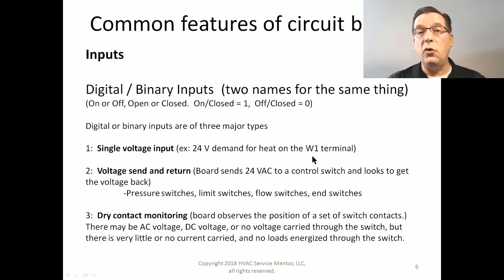Single voltage means there's one voltage it can be. It's either 24 volts or it's 0 volts. It's not in this kind of in-between varying type of throttling thing. No, it's either this or it's that. That's what we mean by binary. That's what we mean by digital. It's either open or closed. It's 24 volts or 0 volts. There's no in-between. A demand for fan on would be 24 volts at G. That's a single voltage input.